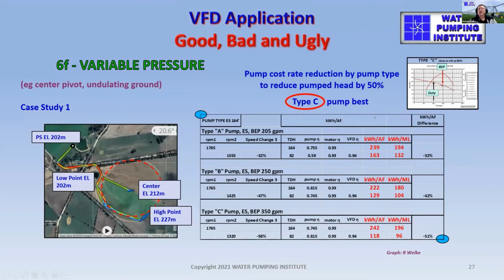So here's the summary. The type C pump was the best, where the duty is far to the left of best efficiency point. That usually is the more expensive pump to provide, but in this case it's well worth the money. It had a potential saving of 58, but a real saving of 51. The next was the type B pump, where the best efficiency point is the same as the duty point. That only realized 42%, and the type A pump, disaster situation, only 32%, and the potential to run the pump off the end of its curve.